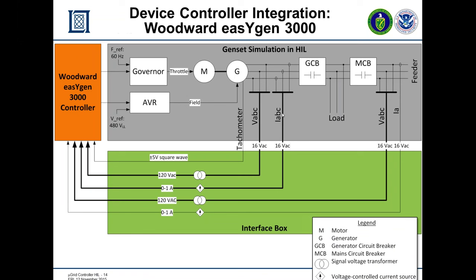We tricked the Woodward EasyGens into thinking they were controlling a real genset by modeling the motor generator and two circuit breakers, creating governor and AVR models. In the Opal RT unit, we took out tachometer voltage-current signals at 16 volts AC, then worked with Opal to develop an interface box that translates those signals — converting 16V AC measurements to 120V AC — which are fed into the Woodward EasyGen, which then controls the simulated genset via AVR and governor signals.